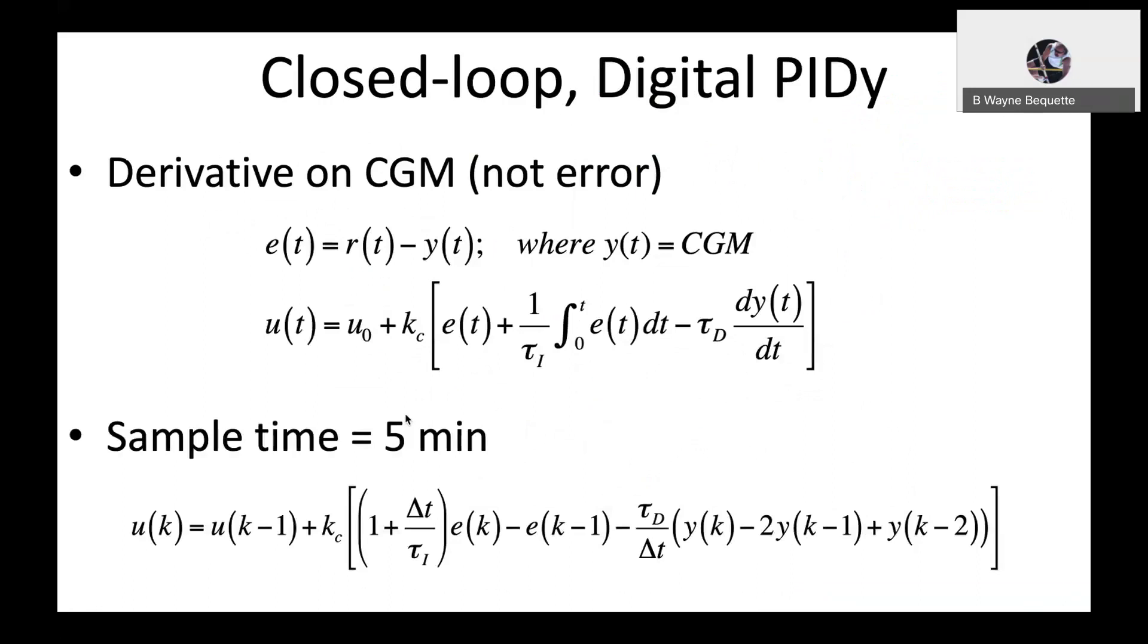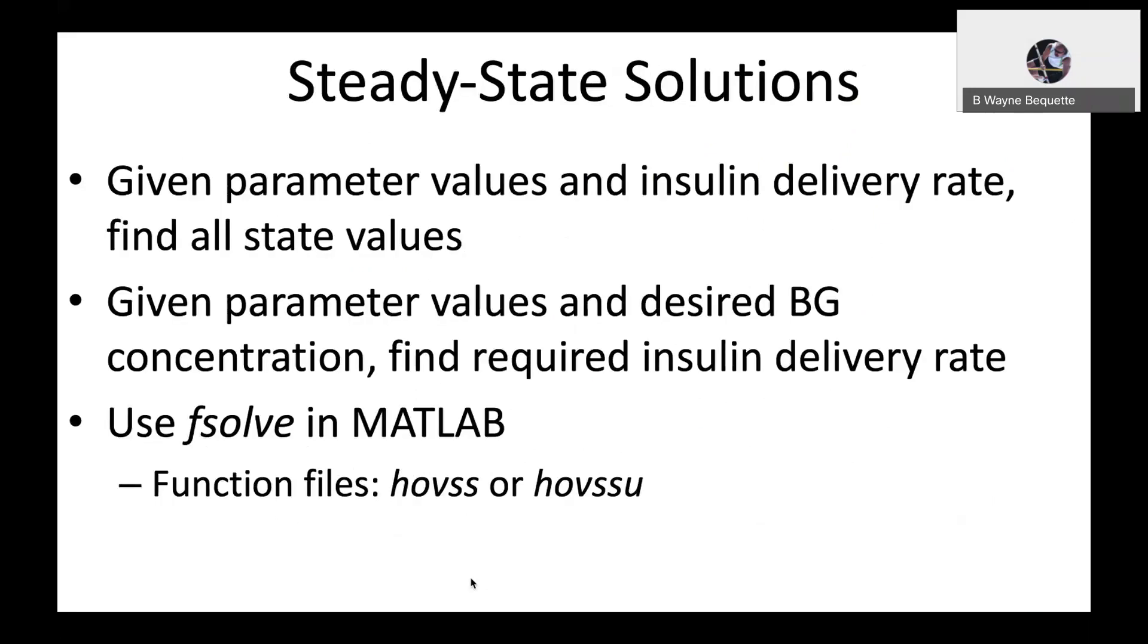The closed-loop controller is a digital PID. The derivative is on the measured glucose signal and not on the error. I show both the continuous representation as well as the discrete representation that's actually implemented. We use a sample time of five minutes.